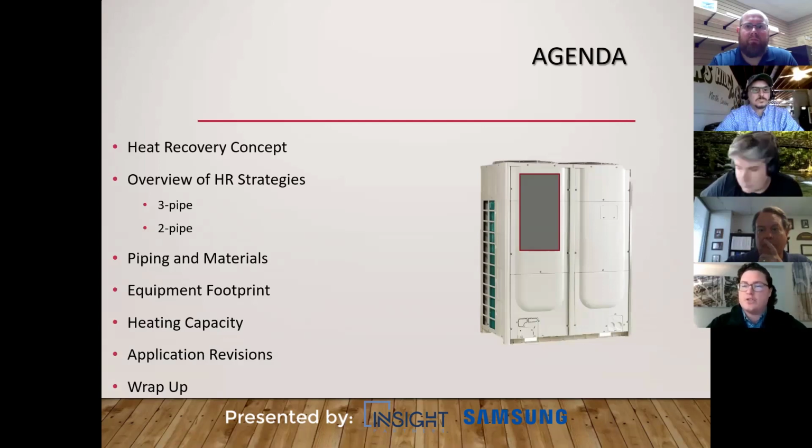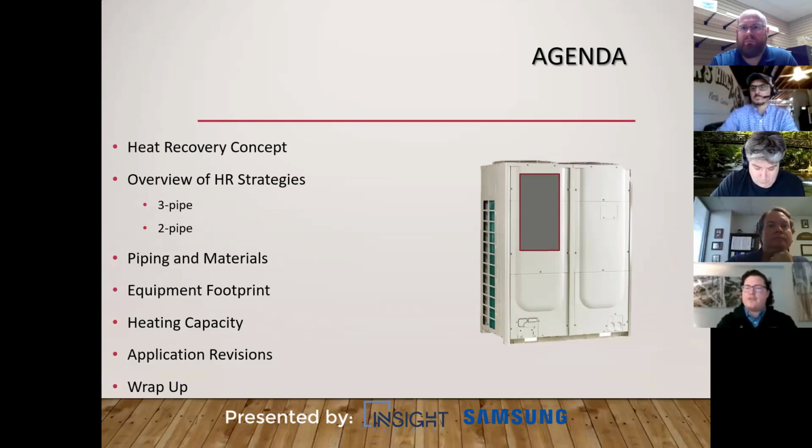Anytime you do a VRF project, the mechanical contractor has to do an as-built design. Originally we put an estimate into any manufacturer's design tools, and we take a look at how much additional refrigerant charge is going to be needed to charge that system properly once it's installed. Before the job is done, this is estimated by taking, I believe Rod uses Bluebeam, to manage the feet of piping on each independent system.